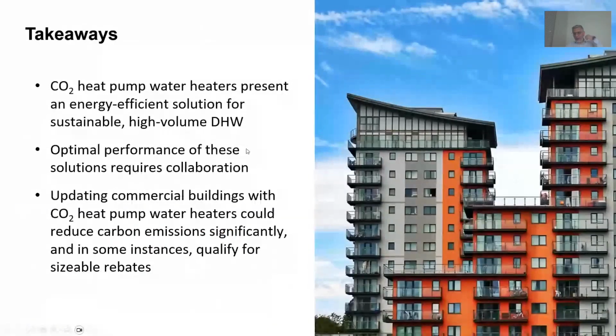So what advantage did we get from there? Since a CO2 heat pump is much more efficient compared to electric resistance heating, and it's an existing building, we use CO2 to provide hot water, so we are reducing the carbon emissions. It was considered a net zero facility, and it was certified as the first passive house hotel.